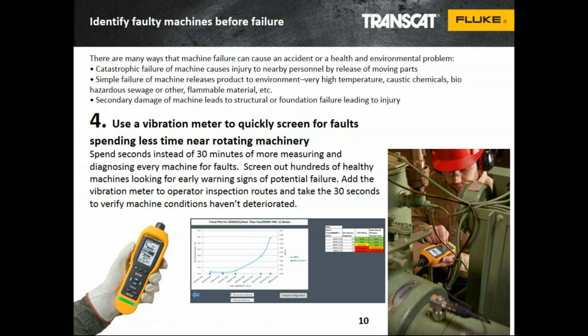It takes high frequency data for bearings, low frequency for imbalance, misalignment, and looseness, and it also takes a temperature reading. Just like a nurse knows what those numbers mean, we've got a database so we know, compared to other chillers for example, whether that vibration level is good or bad.